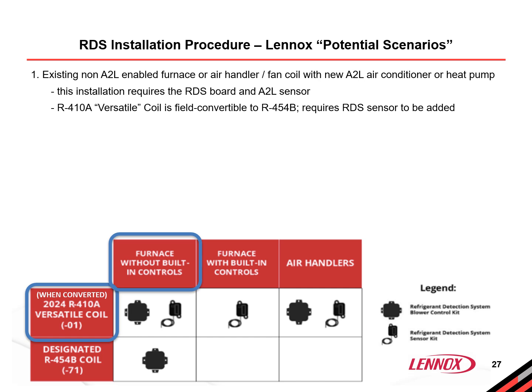This 2024-01 model is convertible at the time of initial installation from R410A to R454B using the RDS coil sensor kit and TXV. However, converting the coil after the installation would violate the safety agency mark and void the warranty. This flexibility at installation allows the dual refrigerant coil to remain in place if preferred when pairing it with a 454B outdoor unit or repairing an existing 410A unit through 2025.